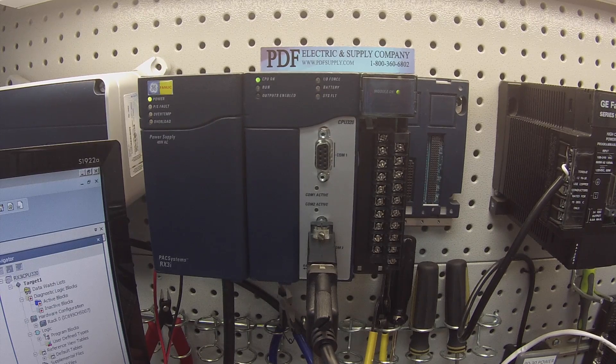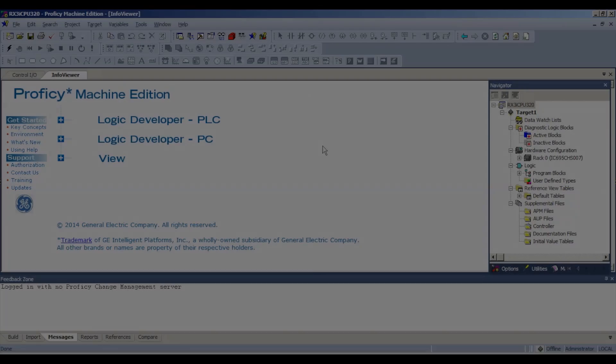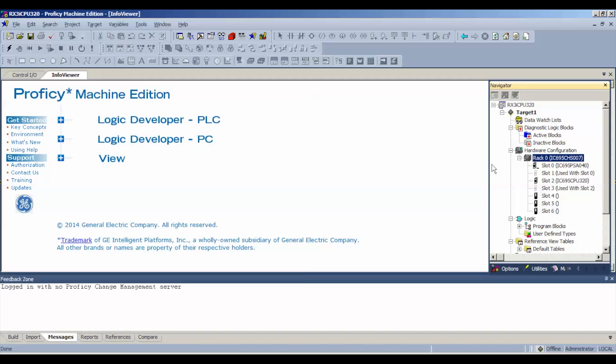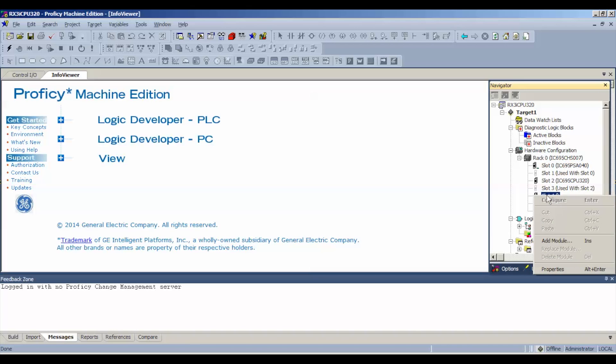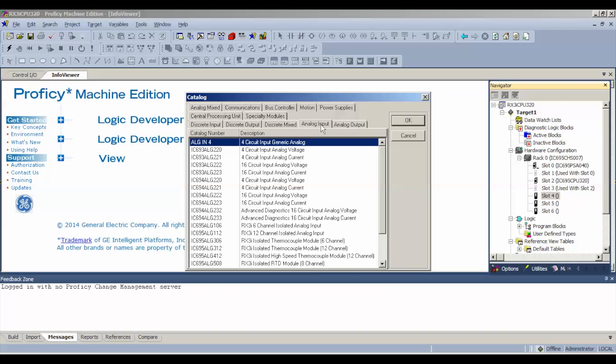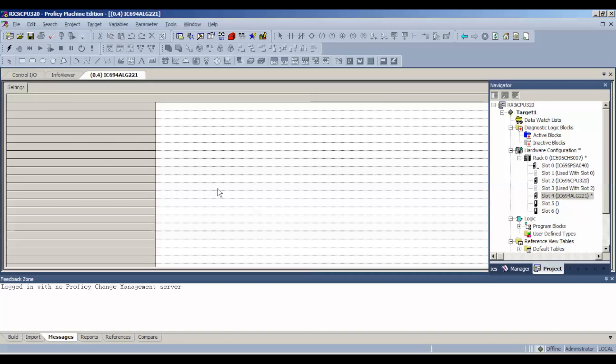Now I'm using Proficy Machine Edition and I've opened up a blank file that will allow me to establish this ALG221 in the slot that it's in. It's currently in slot number four because my processor and my CPU are both using two slots. I'm going to configure it by right clicking on slot four and add module or you can double click on slot four. Go to analog input. We want an IC694ALG221.